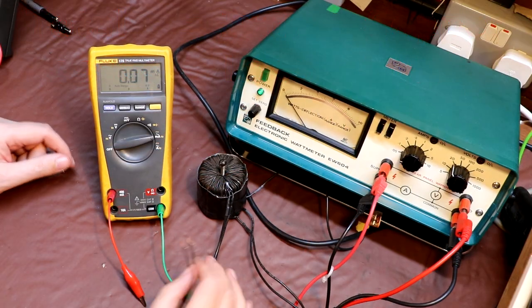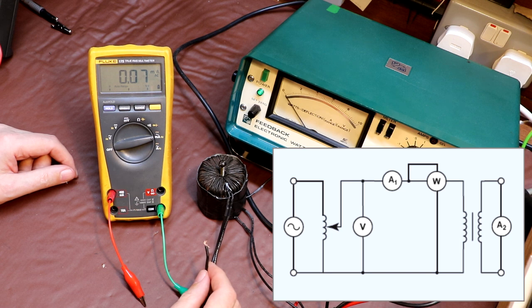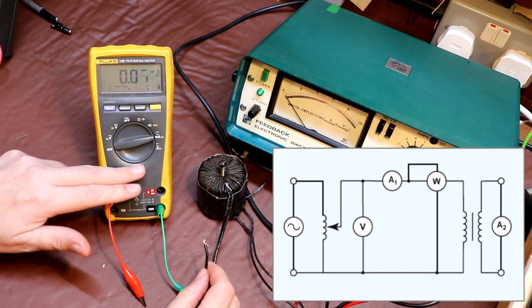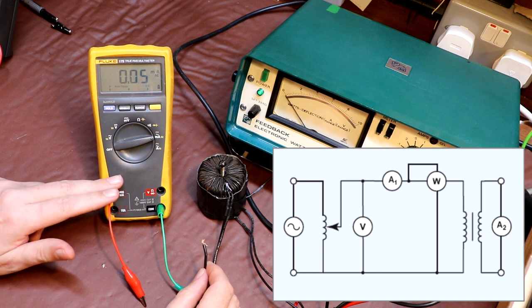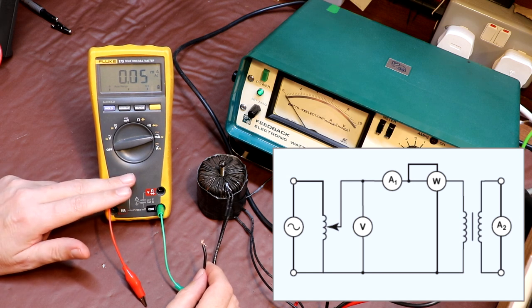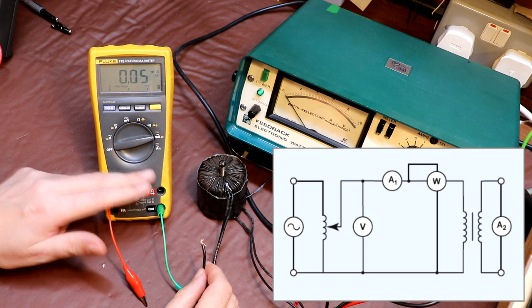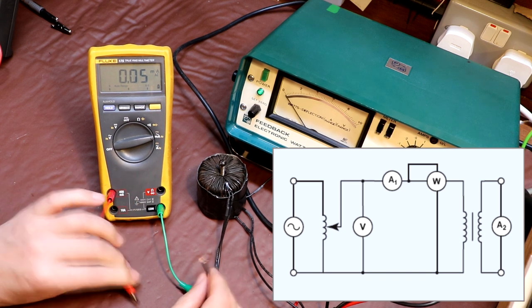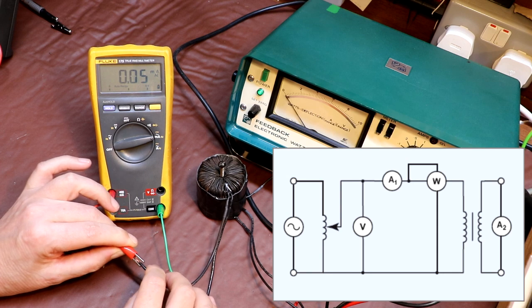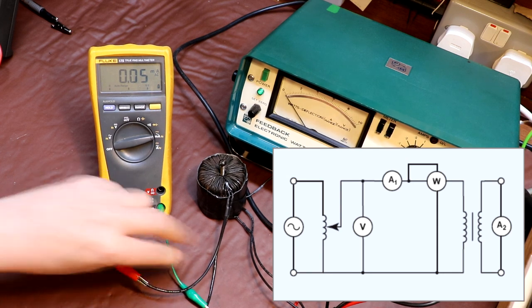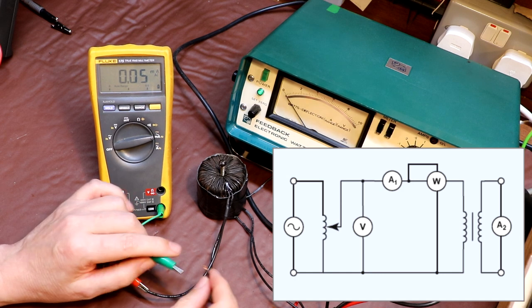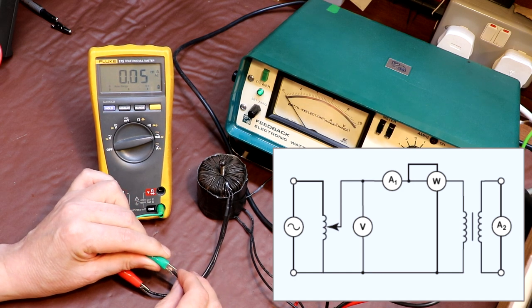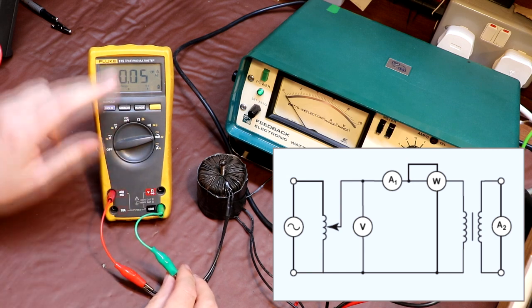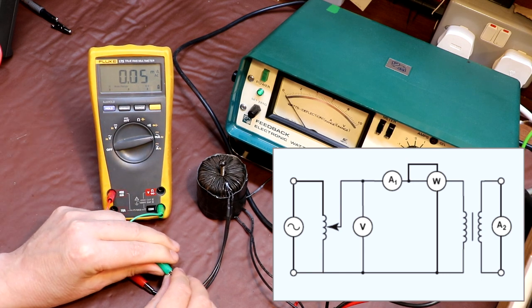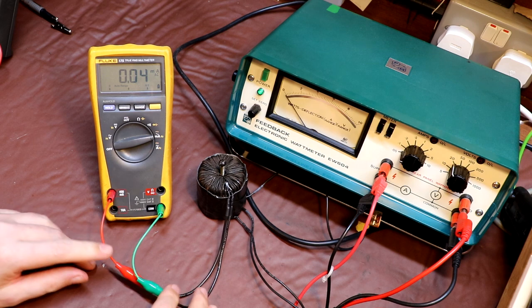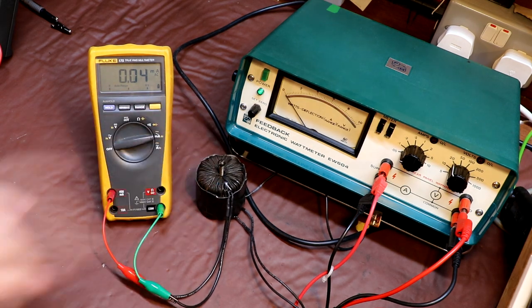For our next test we have to short out the secondary windings of our transformer, and I'm going to short them out using this Fluke meter set to its amp range. The reason I want to do that is because we need to know when the secondary winding is passing its rated current. So let's take the secondary windings and put them into these crocodile clips here. Now obviously we've got to be quite careful when we do this test. We've got to use the variac to wind up the voltage until we achieve 20 milliamps on here, and we've got to be very careful, because if we're not careful we could burn out the transformer if we put too much voltage on the primary.